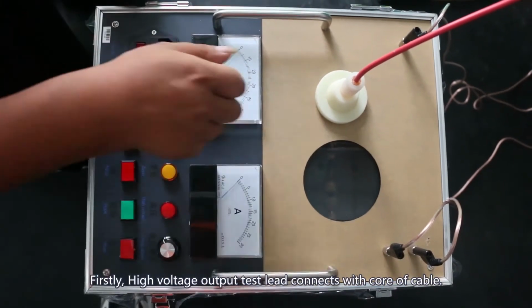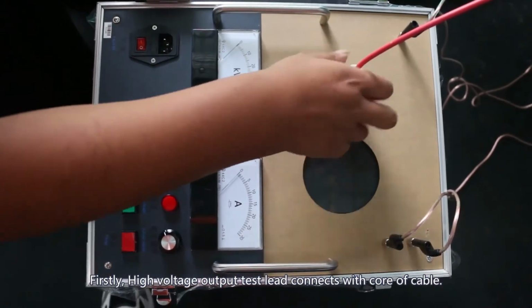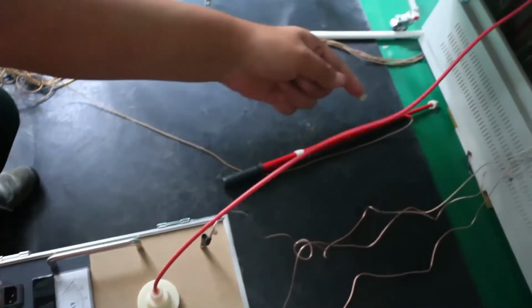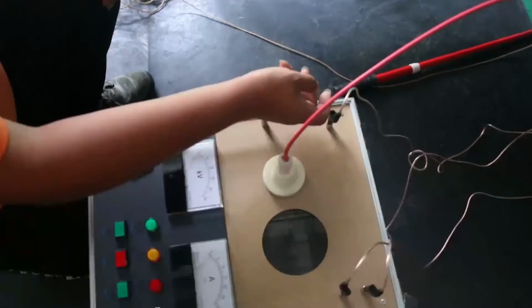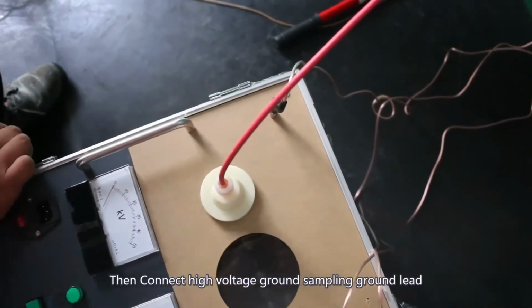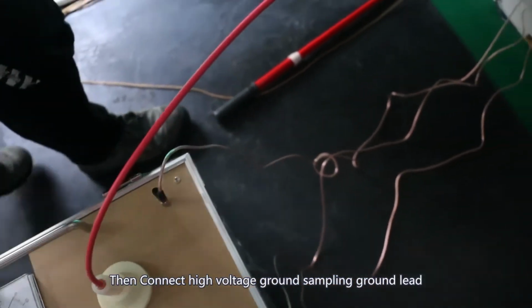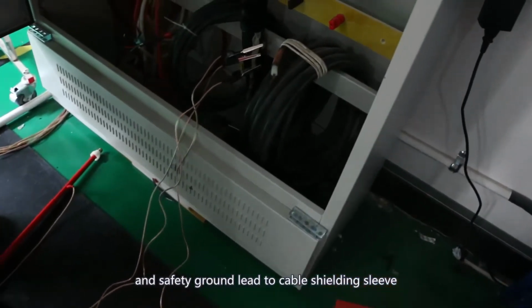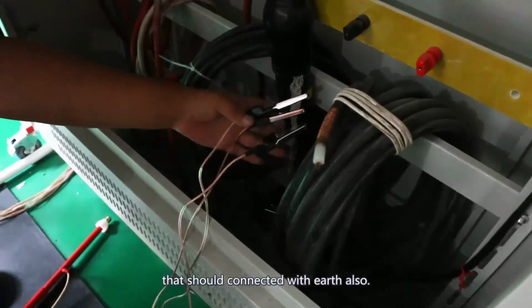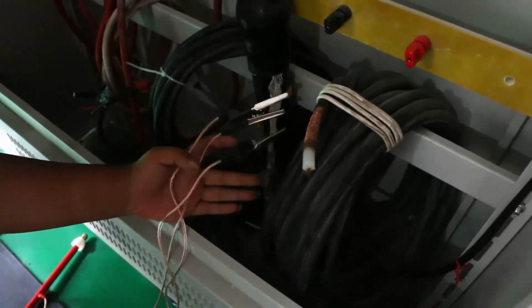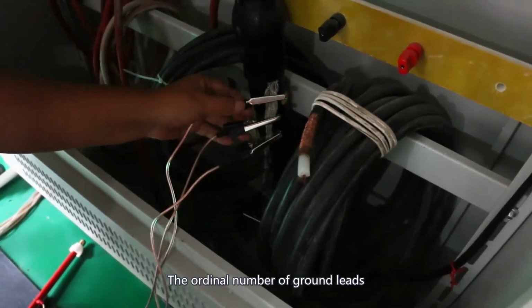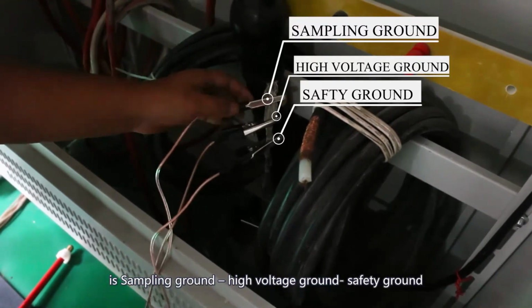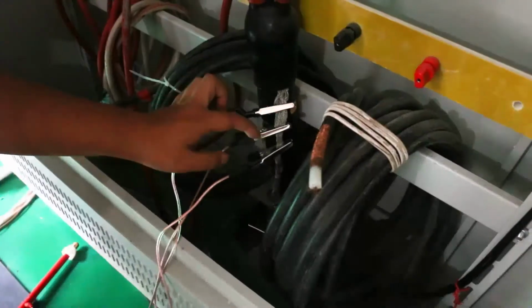Firstly, high voltage output test lead connects with core of cable. Then connect high voltage ground, sampling ground lead and safety ground lead to cable shielding sleeve that should be connected with earth also. The ordinal number of ground leads is sampling ground, high voltage ground, safety ground.